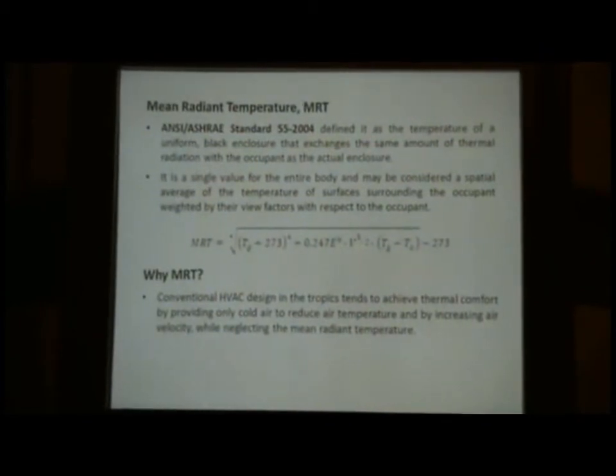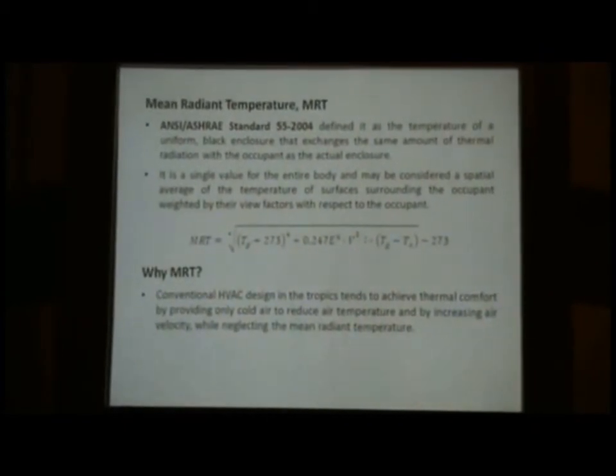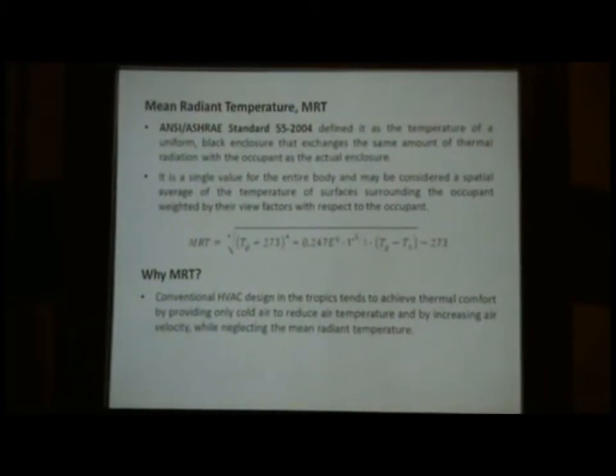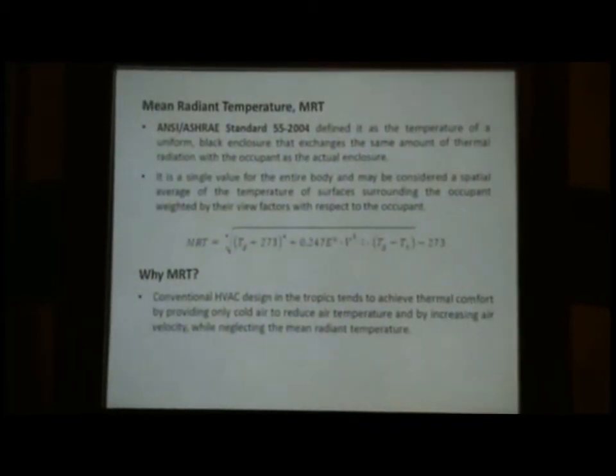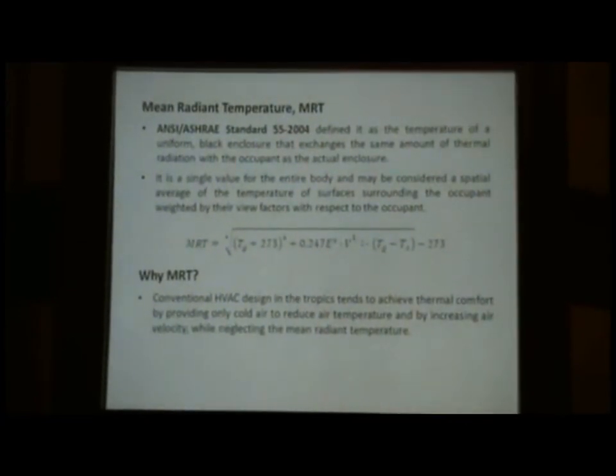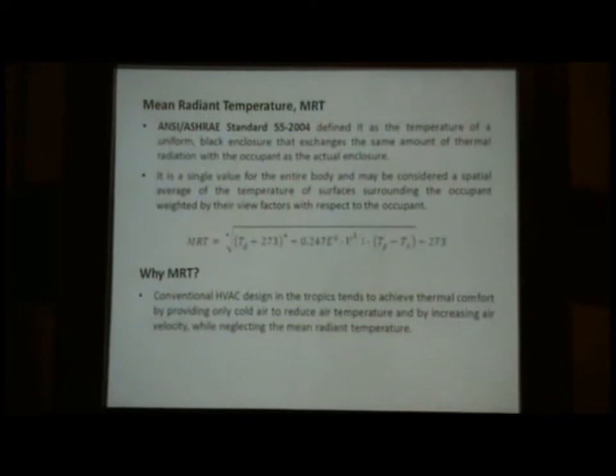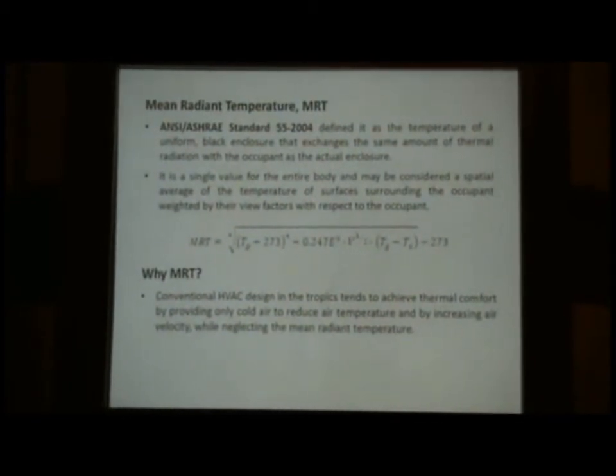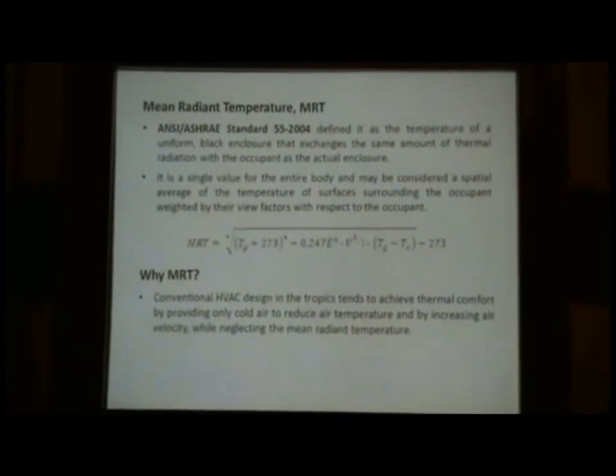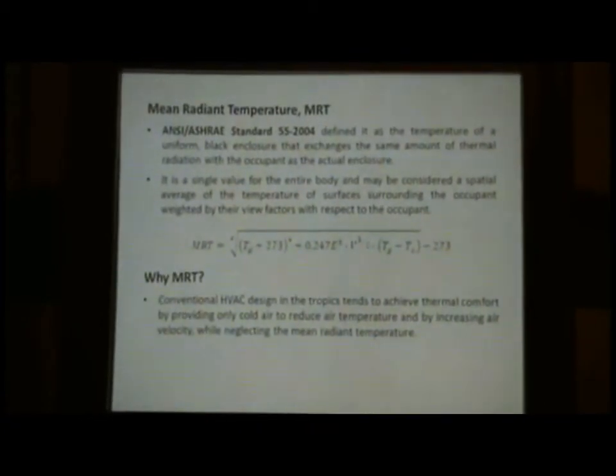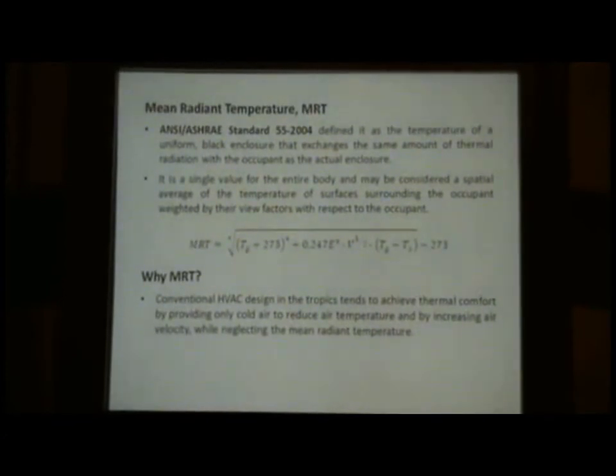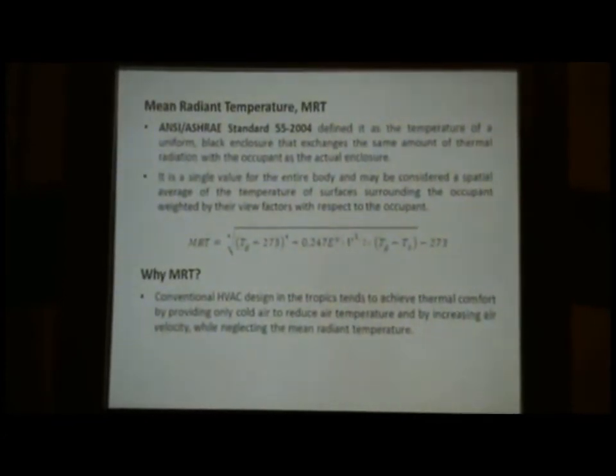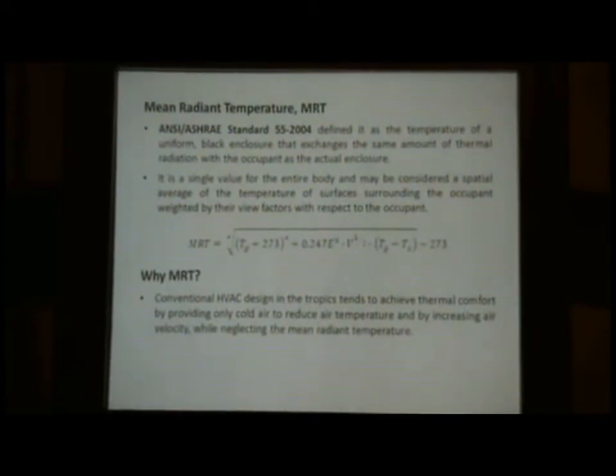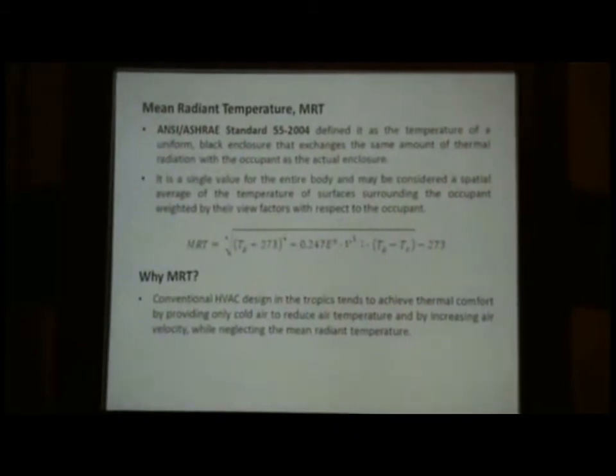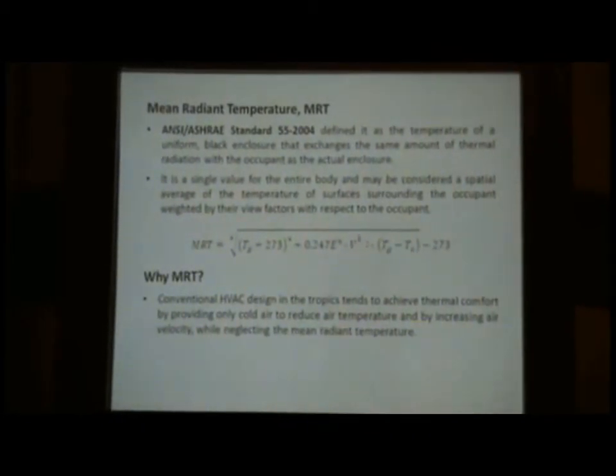And this will have an impact on the control. Why? Because the control system will use a sensor to look back into this temperature. So what's the feedback loop here? It is basically your space temperature, and your space temperature will have some impact on this, which is G. G here is actually the globe, the black globe temperature. It's special equipment which can measure the globe temperature. The globe temperature finally comes with this complicated equation, and you have a mean radiant temperature. With the mean radiant temperature, you can go into the tools to calculate the mean radiant temperatures.